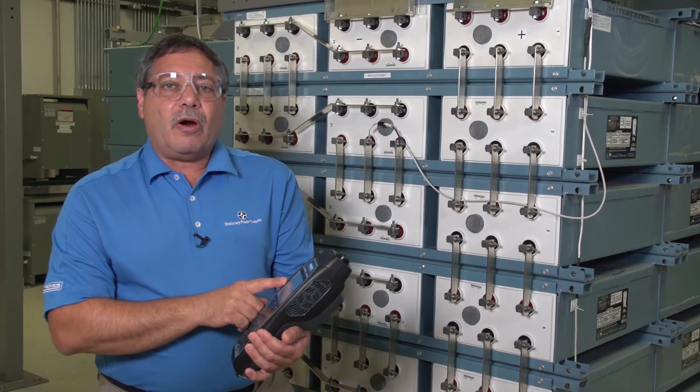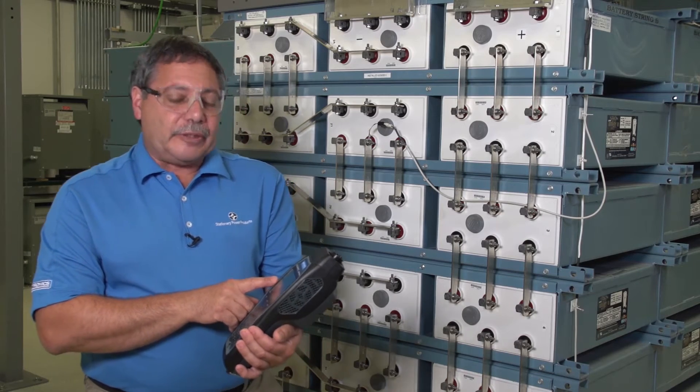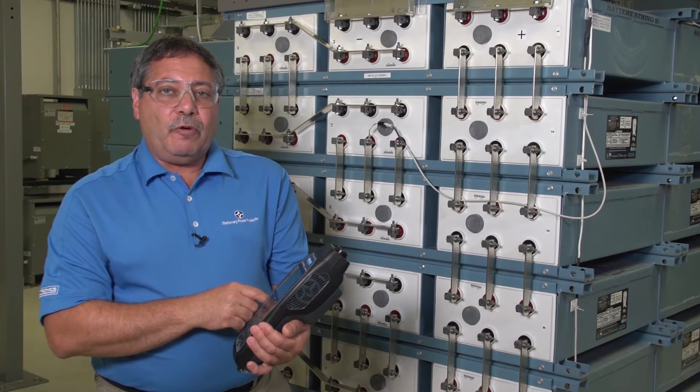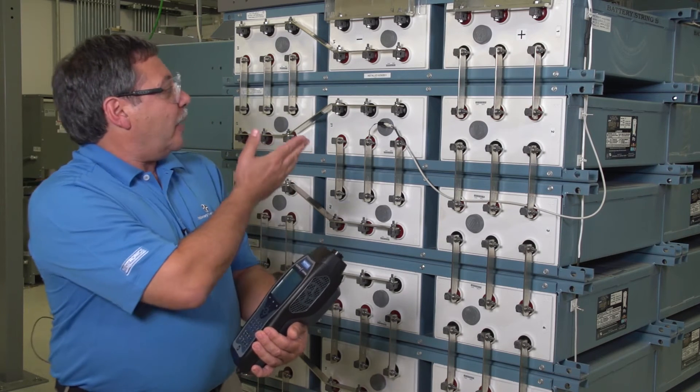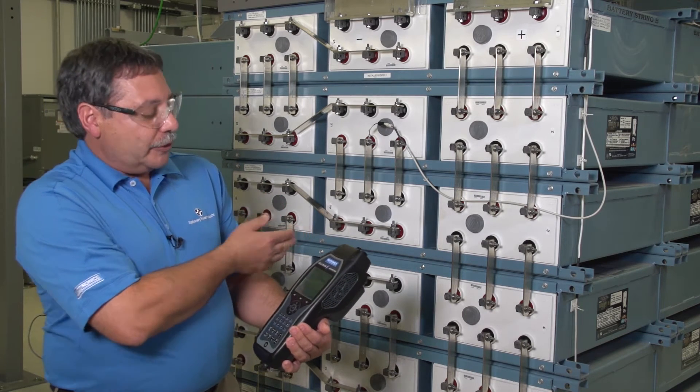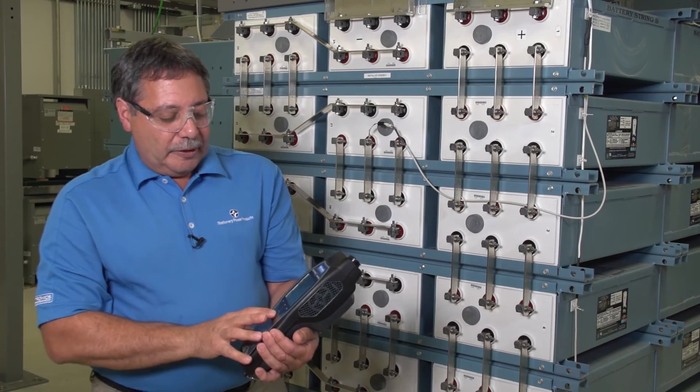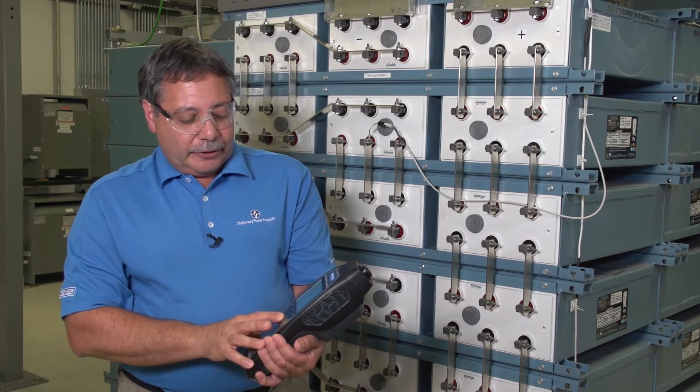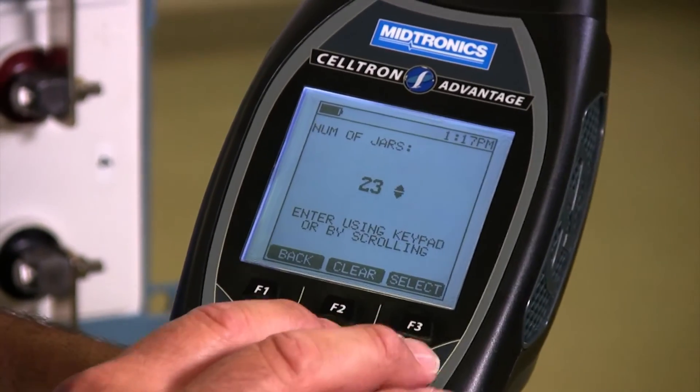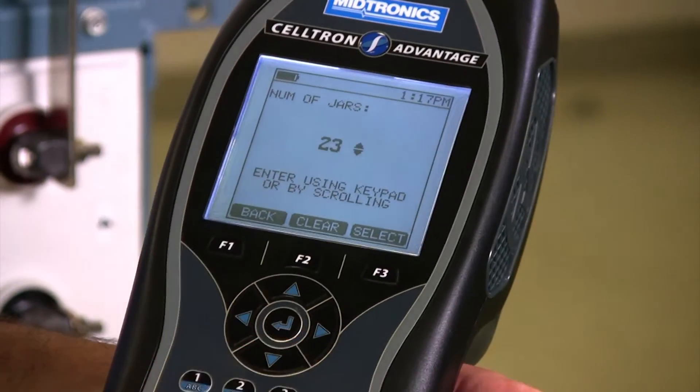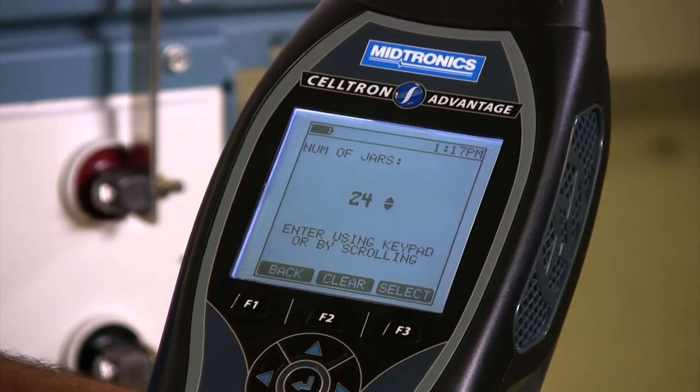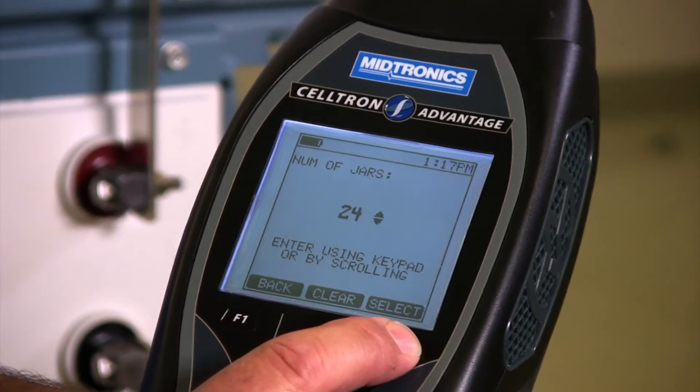First we want to know the number of jars or cells or batteries that we're going to be testing. The default is 24. Happens to be that the string of batteries we're going to be testing today is 24 cells. So I could leave that. But if I had to change it, you just drill into the menu. You could scroll up and down to change things, or you can enter the value in with the keypad. So here I'm going to have 24. Select.